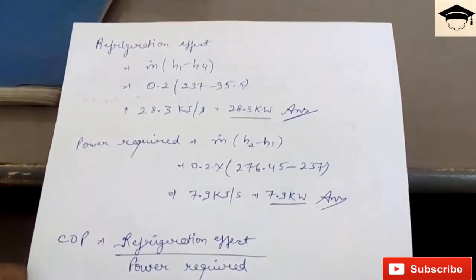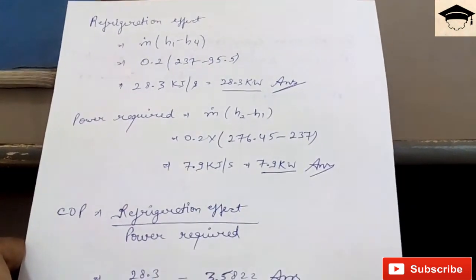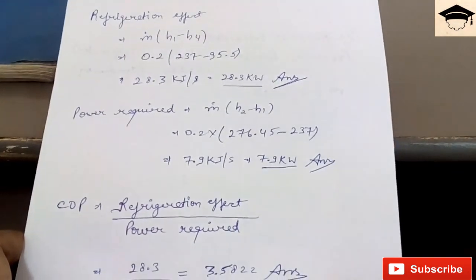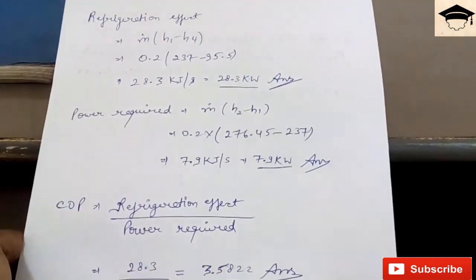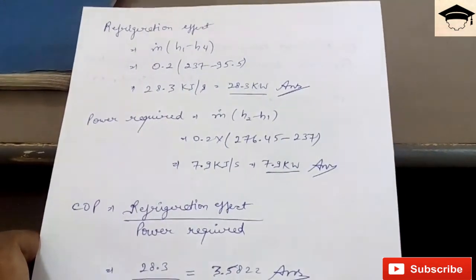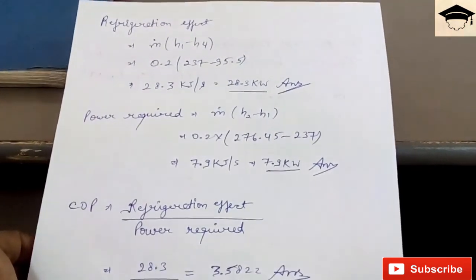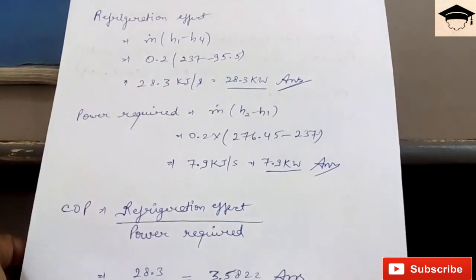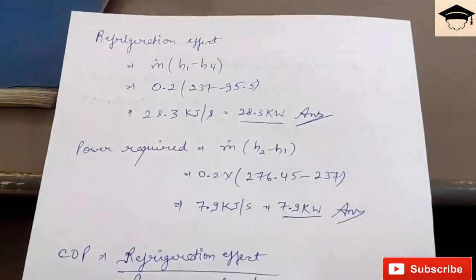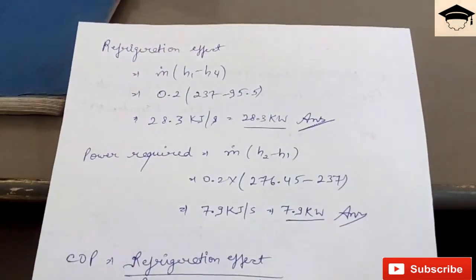Now power required will be mass flow rate into (h2 minus h1). You know the corresponding values from the chart, you substitute and get 7.9 kilojoules per second or 7.9 kilowatts. COP, coefficient of performance of the refrigerating system, is given by the ratio of refrigeration effect to the power required in the compressor. So 28.3 divided by 7.9 kilowatts gives COP equal to 3.5822.